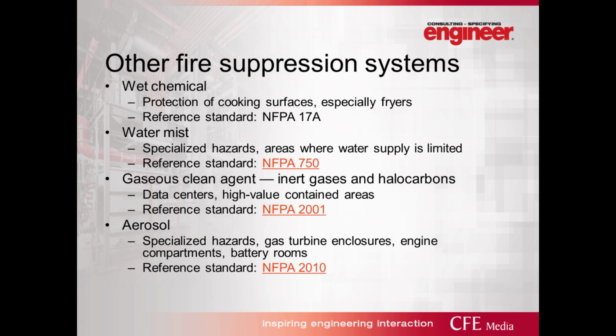Water mist is a very specialized method of applying water in very small droplets and is used for a lot of different hazards. Also very good where water supply is limited because in comparison to sprinkler systems, it uses quite a bit less water.